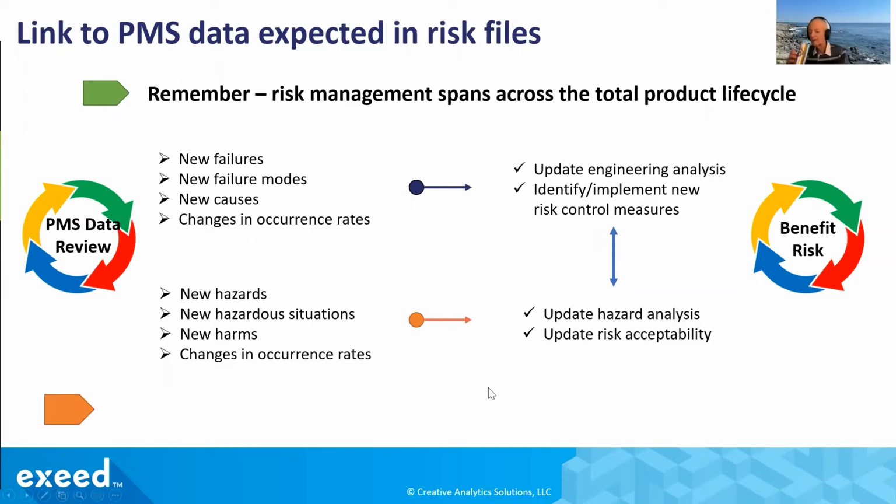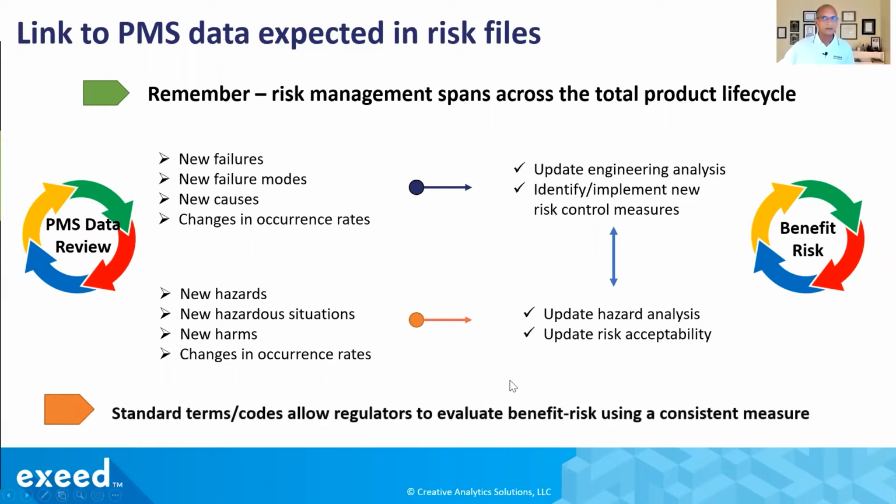Yes. Ed, can you say that document one more time? Yeah, it's 20416. It's a TIR. I'm looking for my copy here so I make sure. Yes, ISO TR 20416, Ed. Medical device post-market surveillance for manufacturers. We can post that in the chat also, if Ed, if you don't mind doing that. I will do that. It's a 2020 document, so it is fairly new.